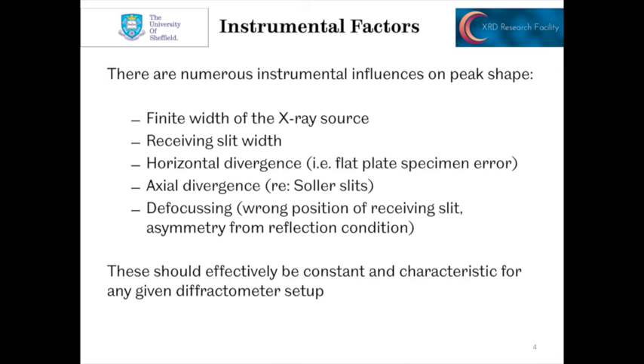We've talked about horizontal divergence before, this kind of flat-plate specimen error, the fact that we don't have a sample that sits perfectly on the diffraction circle. We've mentioned Soller slits in the past as well, and the effect that this can have on axial divergence. That's given as an asymmetry on the lower angle side of our peaks if we're not careful. Defocusing - if we put the slits in the wrong place or we've got some asymmetry from the reflection condition, this can give us some broadening, some asymmetry.